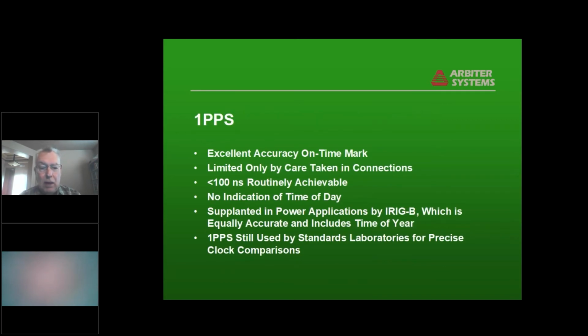1 PPS is used by all the international standards laboratories for precise comparison of clocks to BIPM standard time, for instance. And the reason is because it's got an extremely high accuracy, excellent accuracy on time mark. It can be down to a nanosecond, the rise time of the 1 pulse per second, and limited only by care and execution, really. And 100 nanoseconds is routinely achievable. The standards labs that are comparing time to UTC routinely achieve better than 10 nanosecond comparisons using 1 PPS.